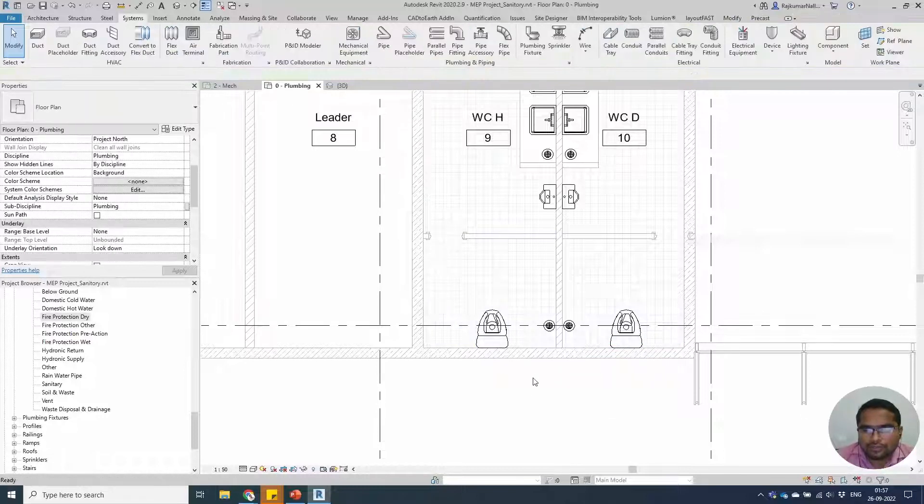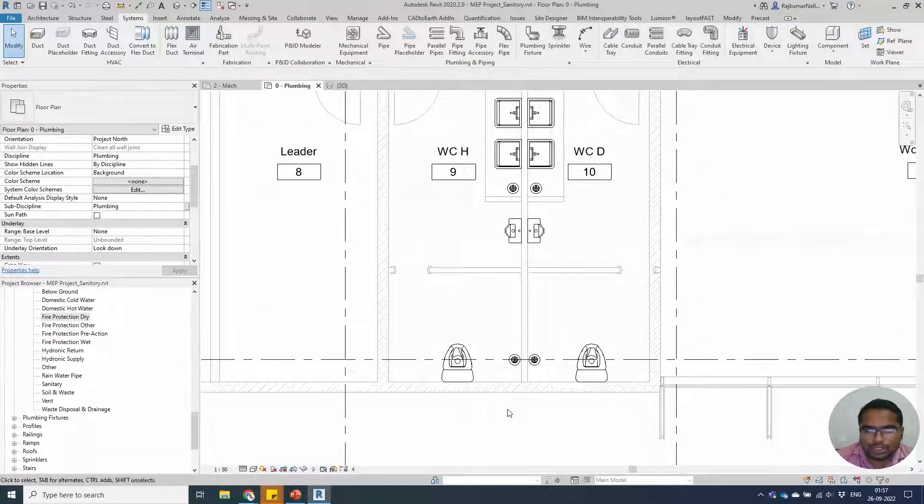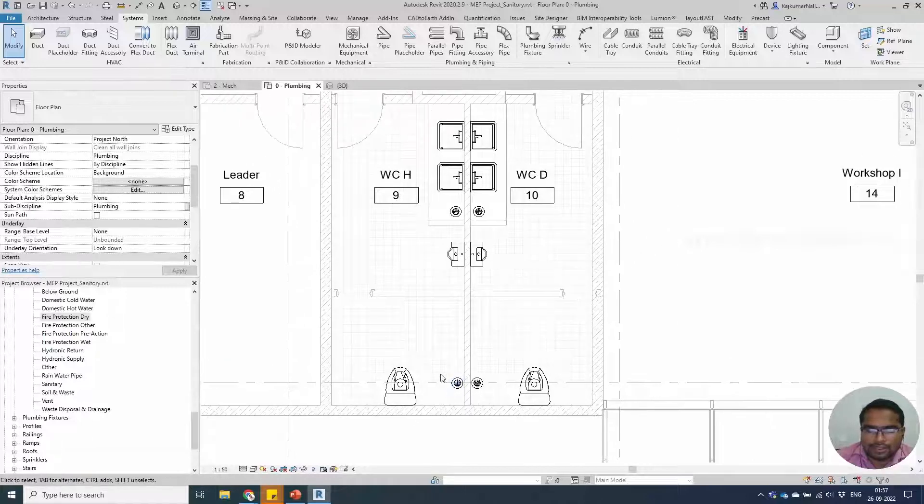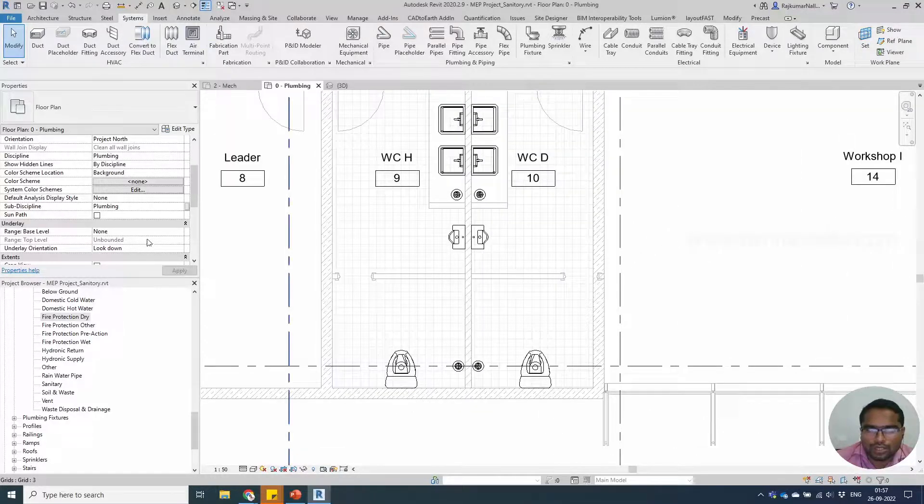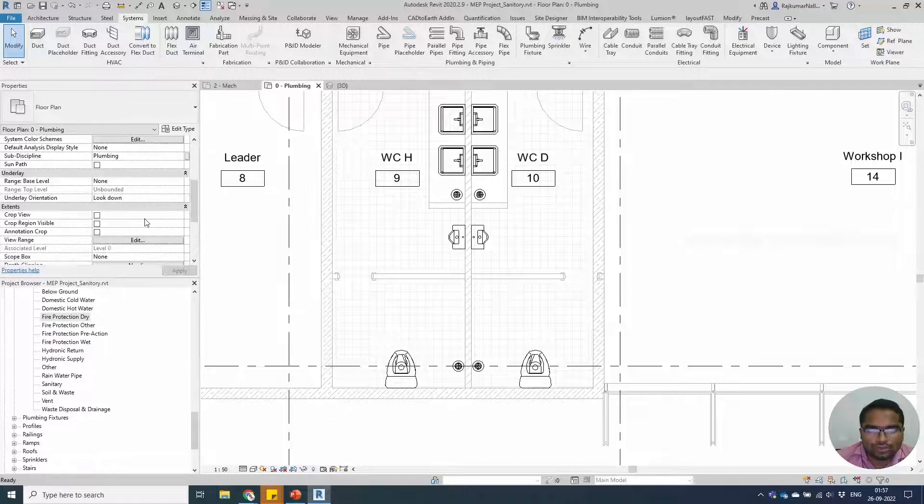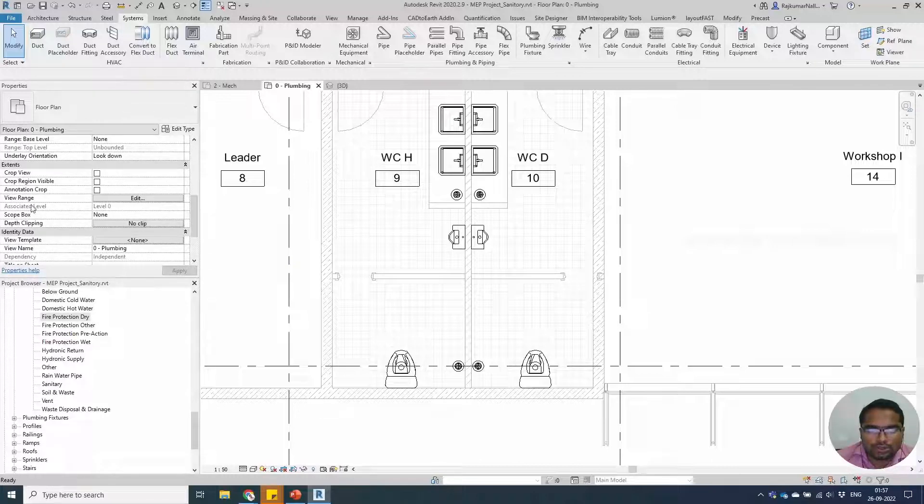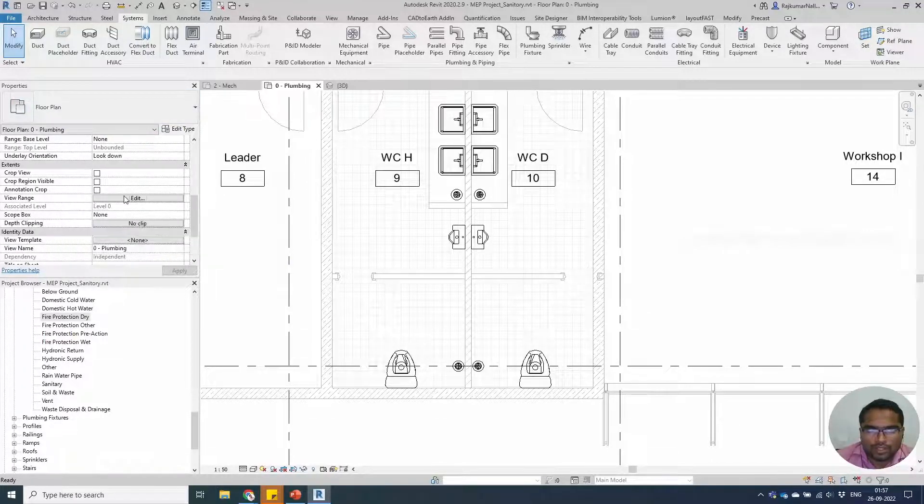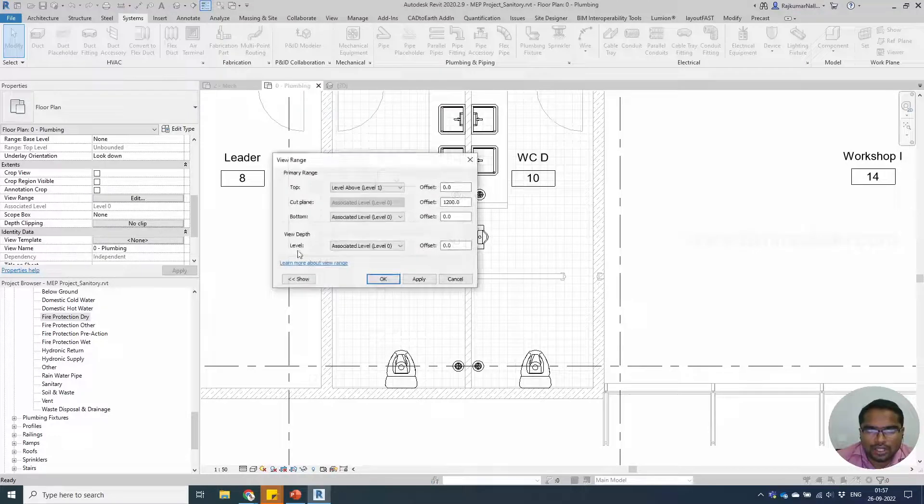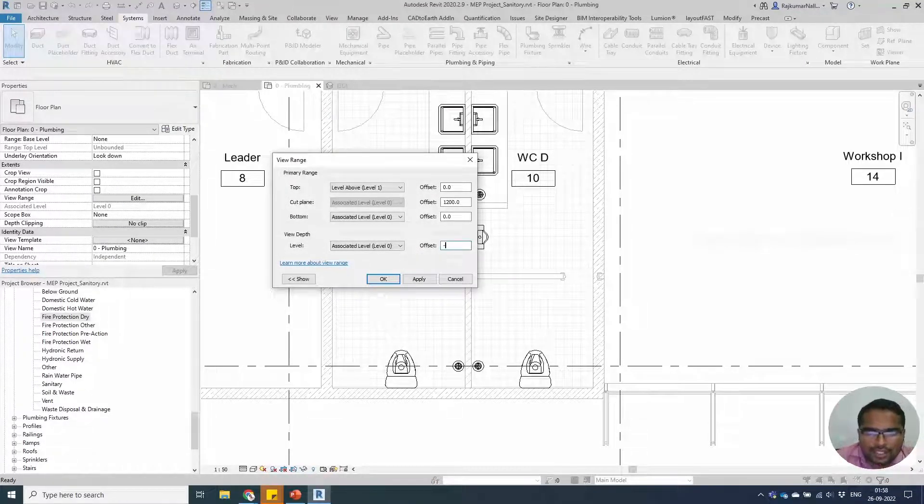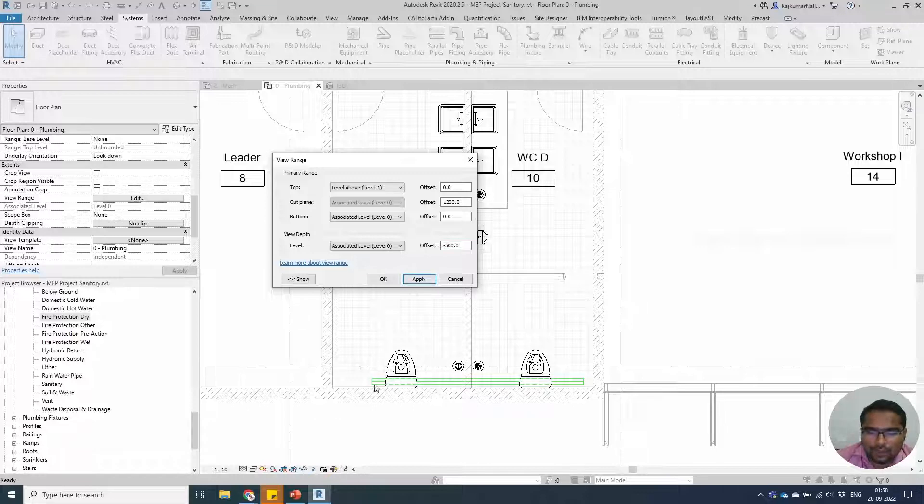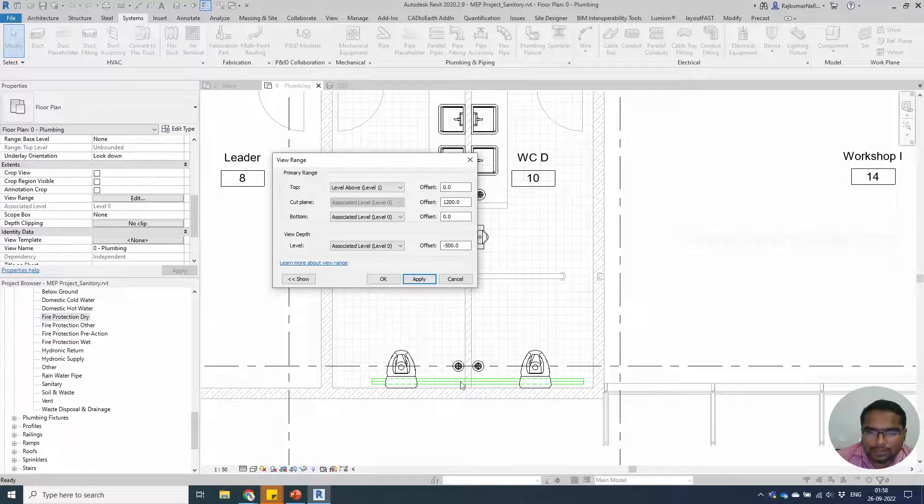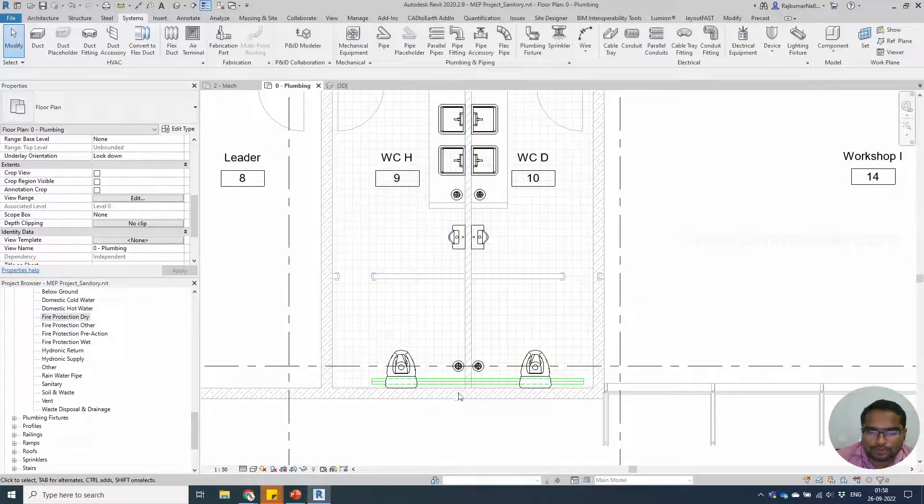When we draw a sanitary pipe work at the minus level, Revit won't allow us to show below the level. We have to scroll down in the property of the view, view range. Edit the view range and change the level depth to minus 5. Apply the setting and we will be able to see the pipe.